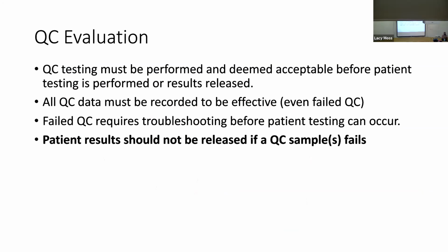You must record your QC data, even if it failed, because failures can tell us what went wrong. And then if your QC fails, you need to do some type of troubleshooting. Sometimes that's just repeating it one time and going, okay, random error, it just fell out that one time. Now it's back in, we're good. Other times it's like, something has gone wrong. I need to figure it out. And you should never release your patient results before your QC has passed.